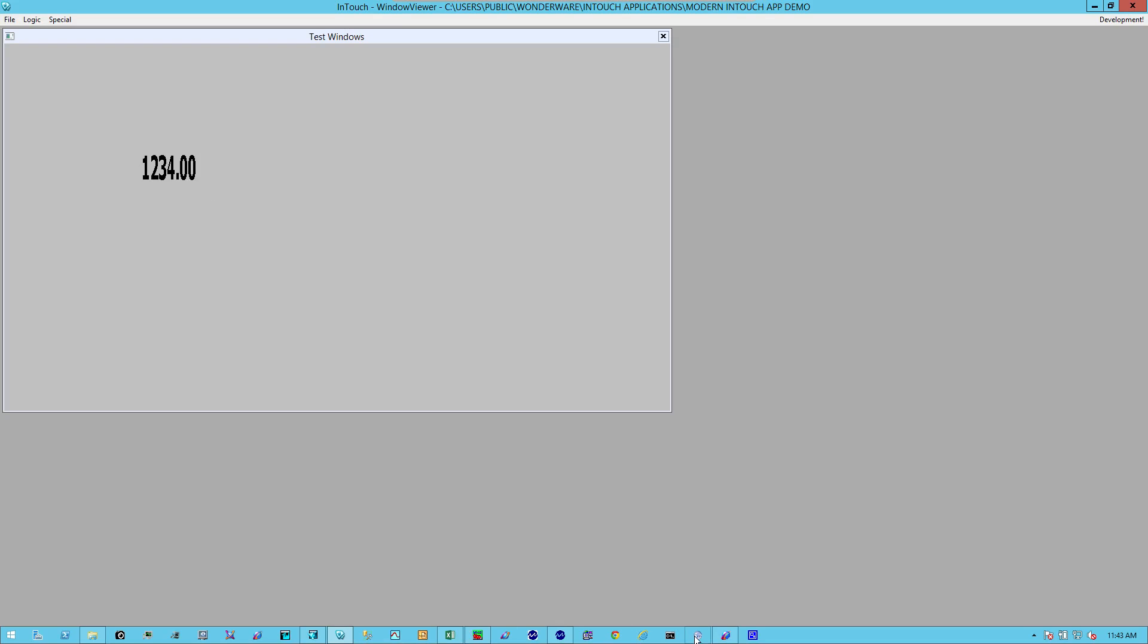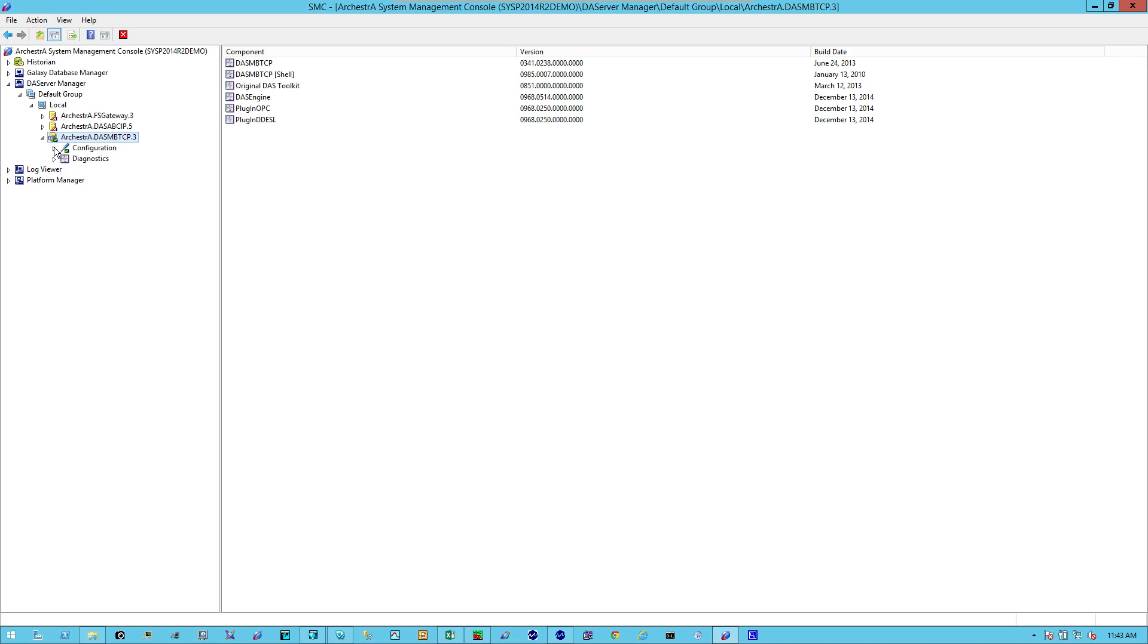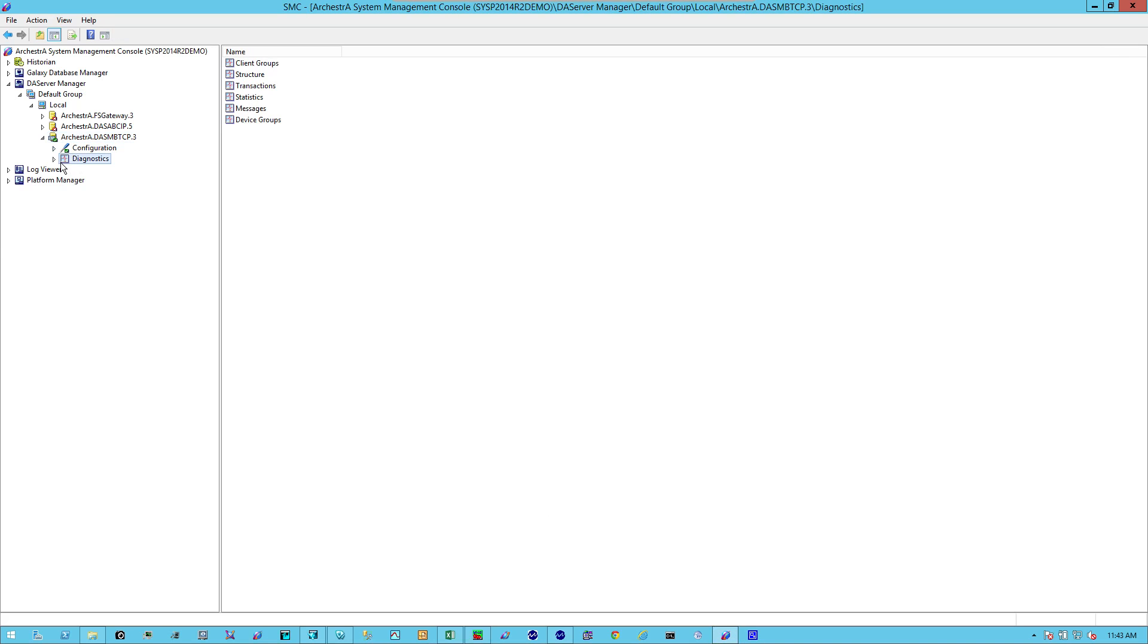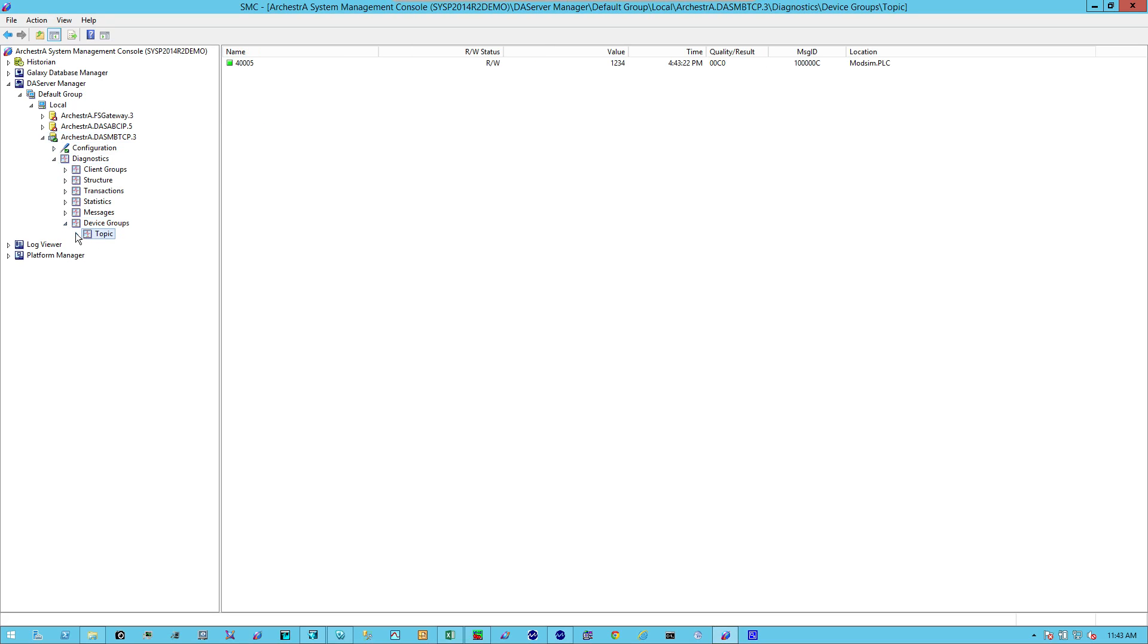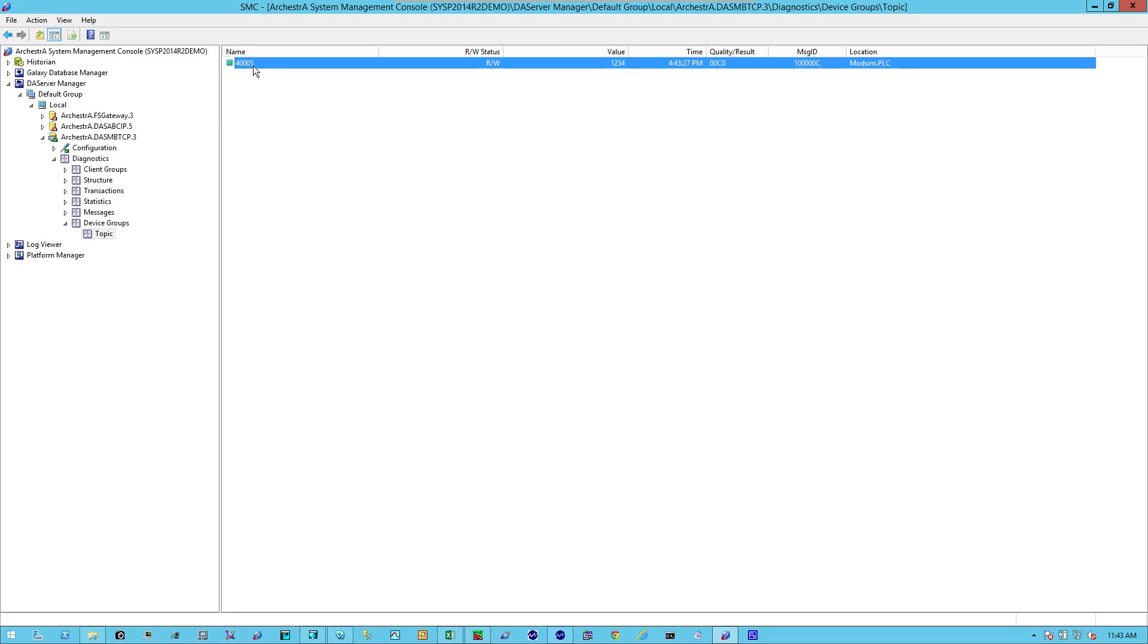If I open up the systems management console, I'll look here. Under my diagnostic view, go to device groups. I see my topic. And as you can see at address 40,005, the value of one, two, three, four. This concludes the brief demonstration on how to configure the Wonderware DA server.